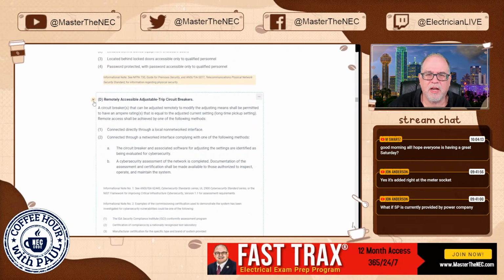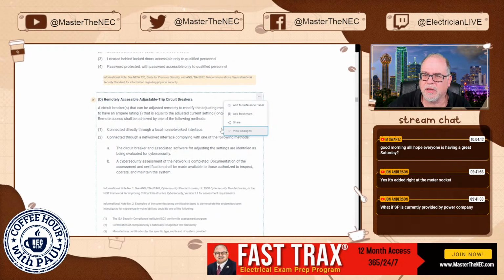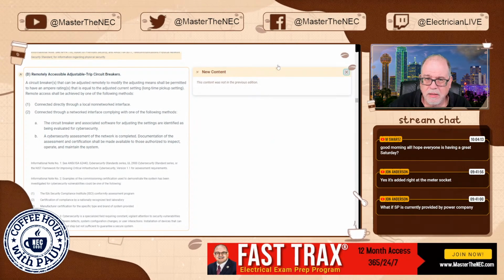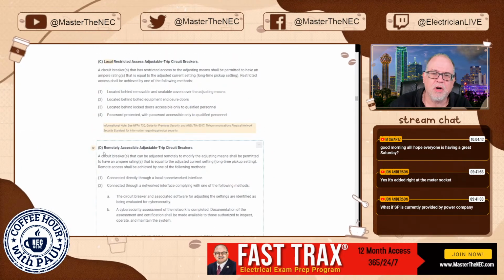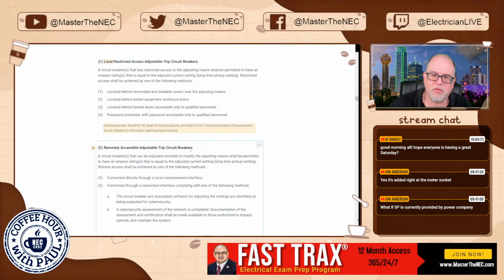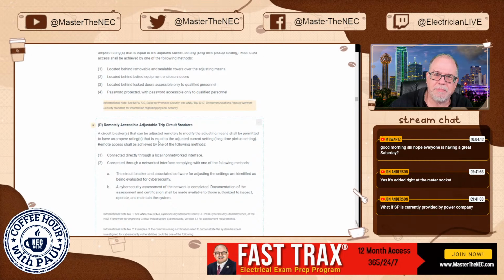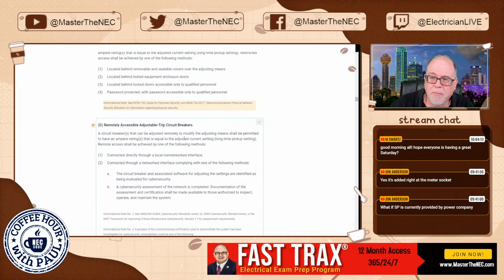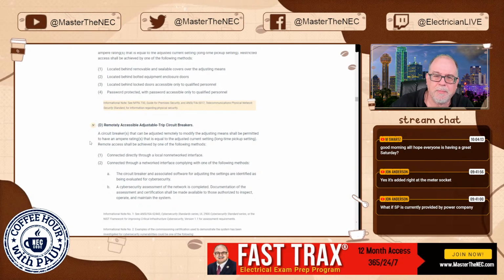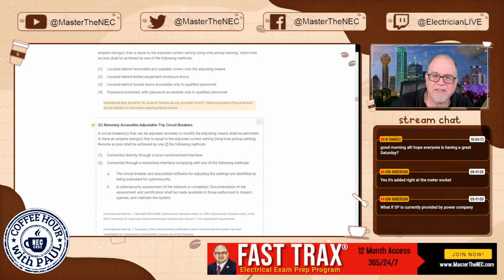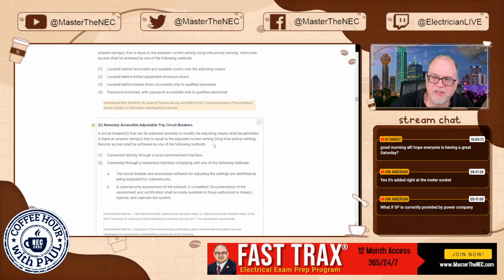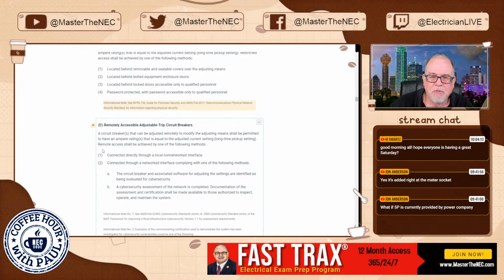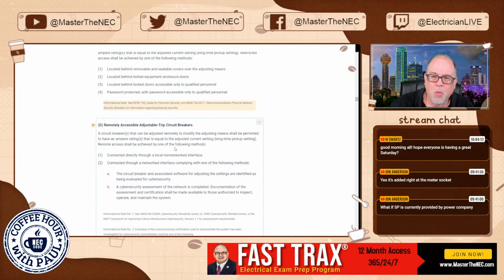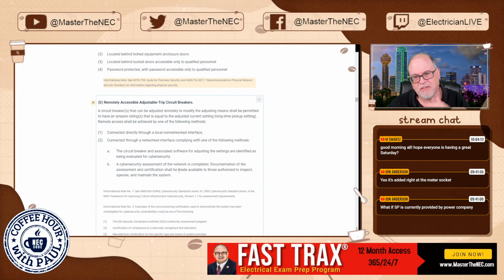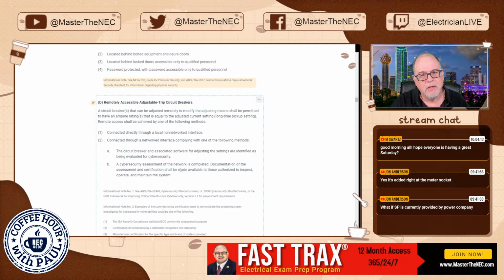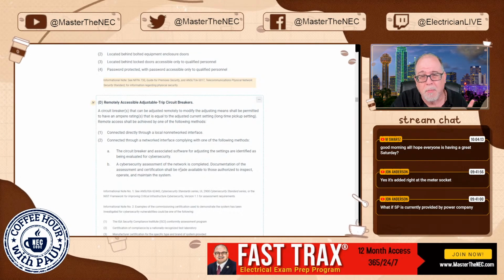So here is a new one here. And if you look here, in the changes, you won't see any change here. But if you look in the National Electrical Code, this is talking about remotely accessible adjustable trip circuit breakers. It says a circuit breaker that can be adjusted remotely to modify the adjusting means shall be permitted to have an ampere rating that is equal to the adjusted current setting, okay, long time pickup setting. Remote access shall be achieved by one of the following methods. And you're just giving some methods to achieve that remote ability to control it remotely, okay?